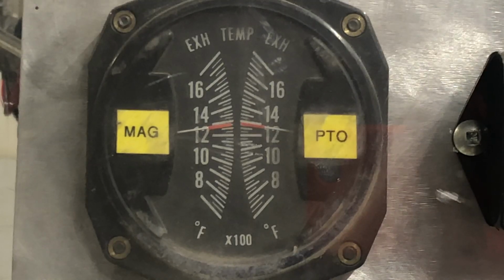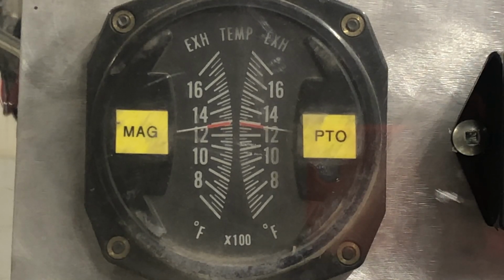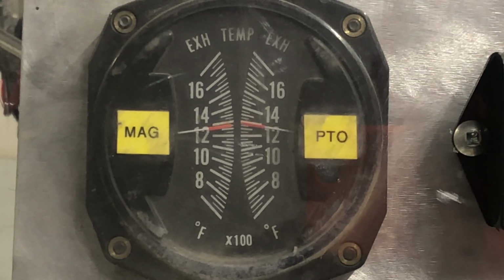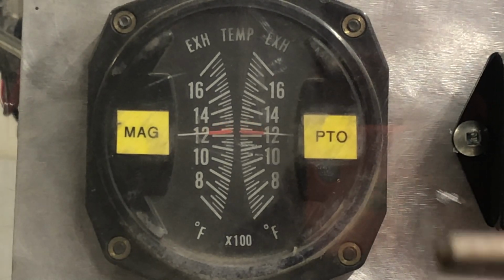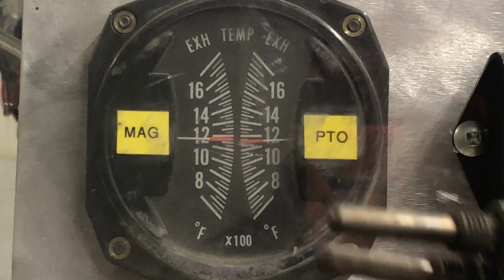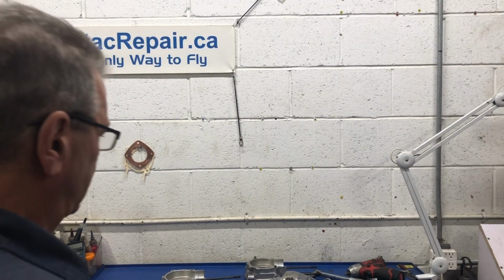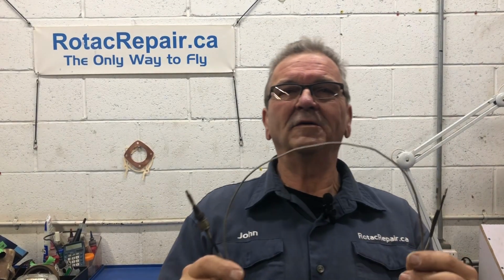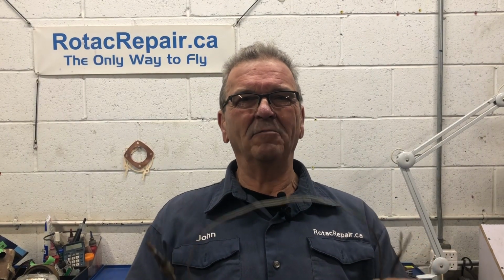Well, that's very interesting. They both started to actually turn red, and I have an identical reading from both of them. So I'm thrilled. So now I know that these are calibrated, and I can use them, and I can rely on the information I get. So that was just by clamping them together and putting them at the torch. So, exhaust gas temperature probe, K-type. Maybe that took the mystery out of what's actually inside of one of these things and how it really works.